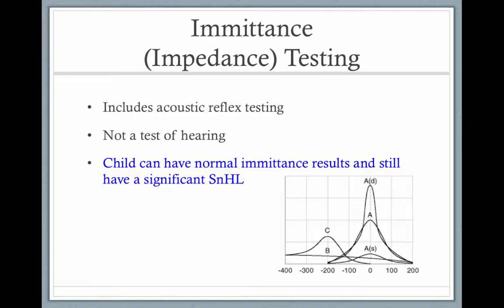Children can have normal admittance tests and still have significant hearing loss. The tympanogram is a picture of admittance — the ease of energy flow — as a function of pressure change in the ear canal. A probe is put in the child's ear, and it feels a bit like going on an airplane where air is pushed in and then sucked out. Measurements of admittance are made as the air is put in and then taken out.